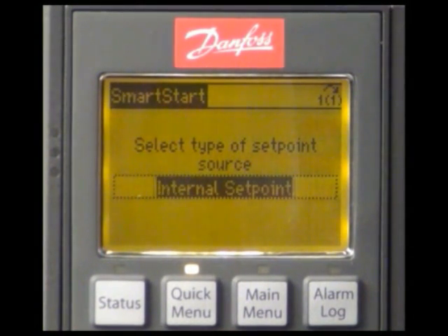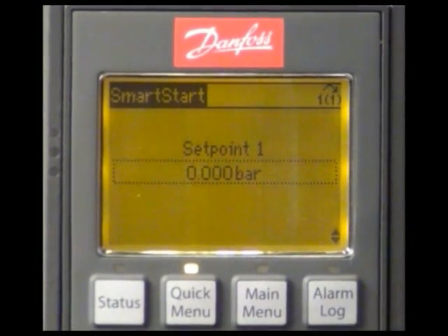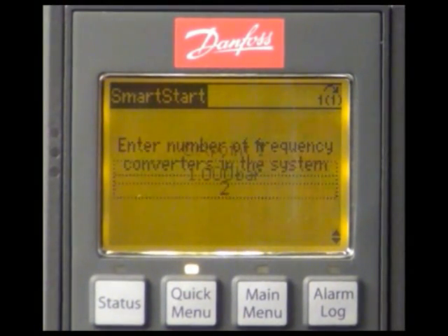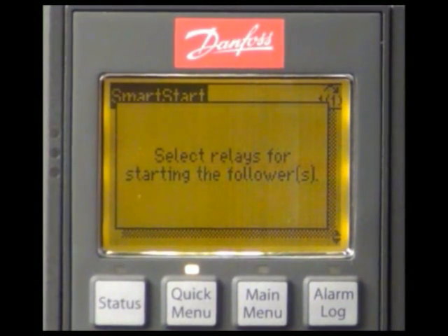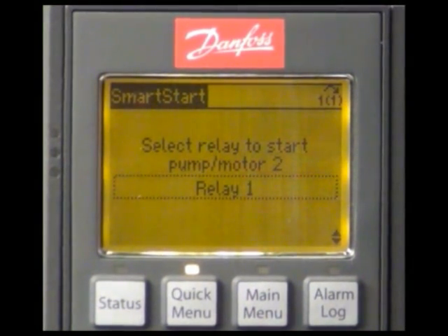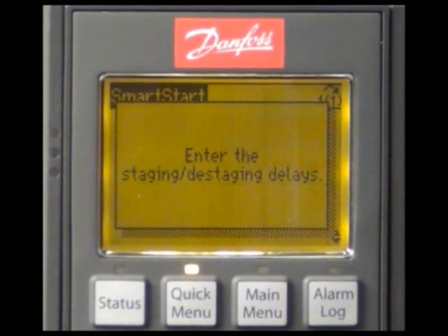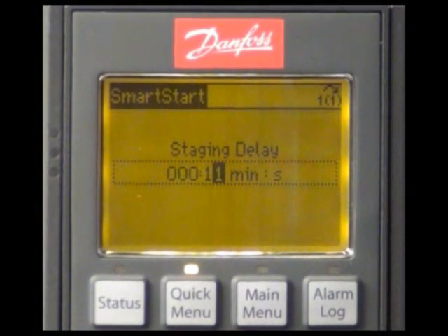We will use an internal set point which means a fixed set point of 1 bar. We will now configure the relays. In our case it is only one relay for starting the follower drive. We want the master to stage and destage with a delay of 10 seconds.